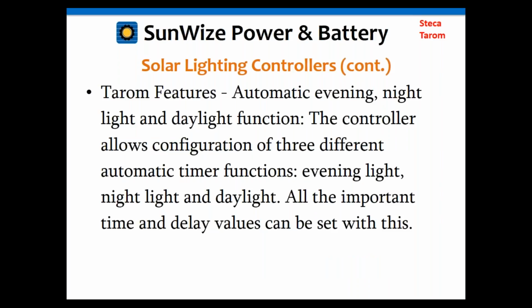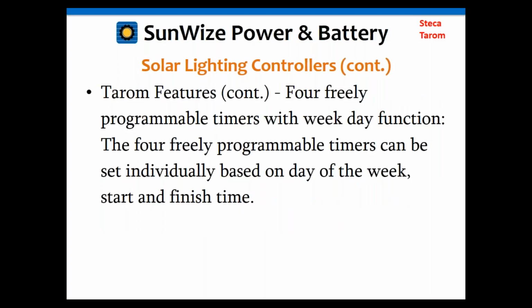So between the automatic evening, nightlight, and daylight function, the configurations basically allow for most mix and match combinations of lighting loads that you would need. In addition to the functionality and control through these modes, there's an additional 4 custom lighting timers that we're going to cover in a sec, which allows you to set additional events purely based on custom timing programming. All right, so next slide.